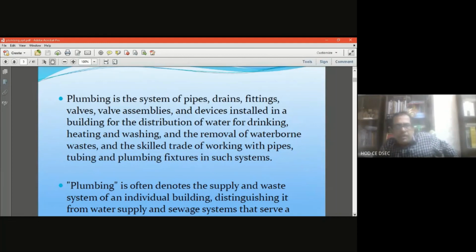But definitely, to get approval of the construction of the building, you need to get the drawing plan of your building approved, and there the underground reservoir has to be shown. If it is not shown, you can't get the approval from the municipal building corporation. This is very important, because the reservoir capacity needs to be checked: how many liters of water capacity you have provided for drinking purposes and for firefighting purposes. So this is very much required.